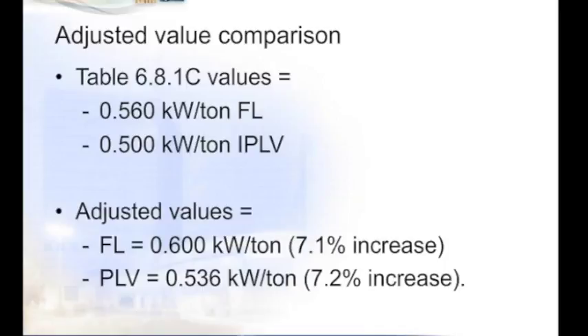So the adjusted value comparison from Table 6.8.1C, we had 0.56 and 0.50, but now with our different operating non-standard conditions, we come with 0.60 kW per ton, which is a 7.1% increase in that energy use, as well as 0.536, which results in a 7.2% increase over the other standard conditions. So this shows that all equipment within the specified operating ranges must comply with 90.1 2010, and for non-standard conditions, the values that you include must be proven by calculations. Now I'll turn it back to Jason, and we will continue.